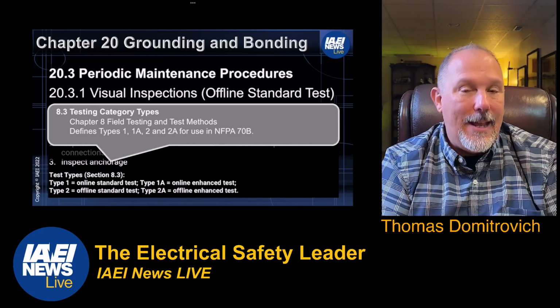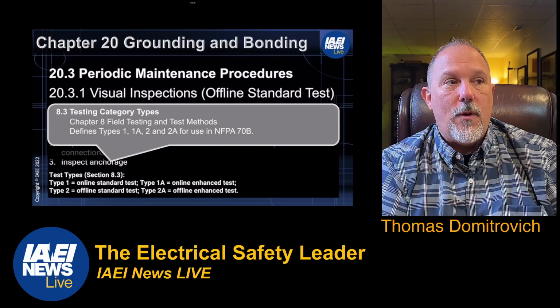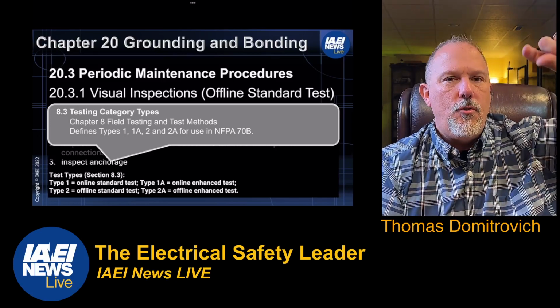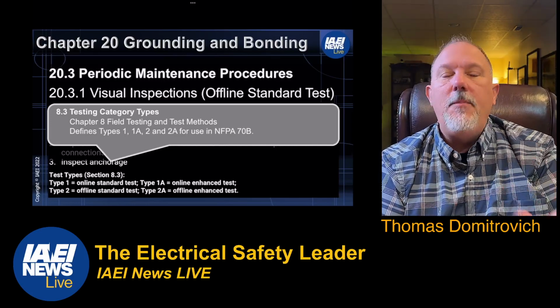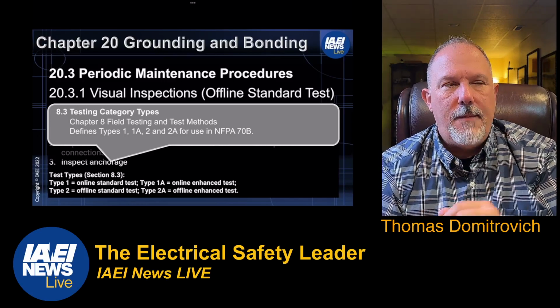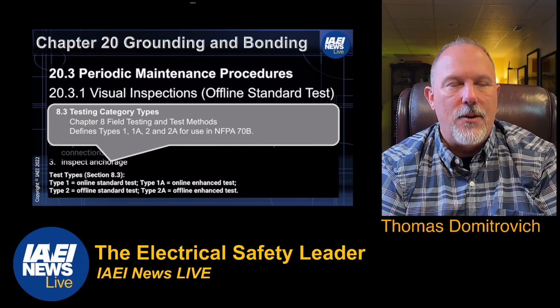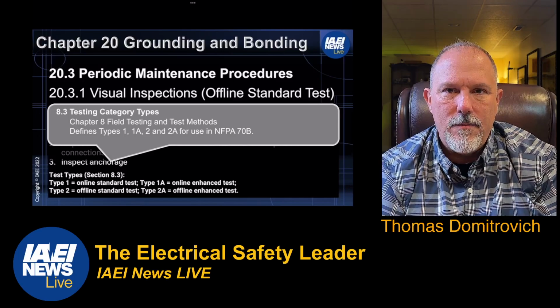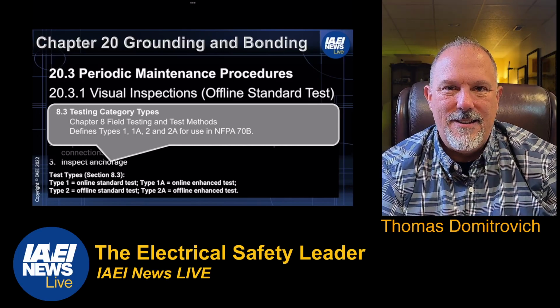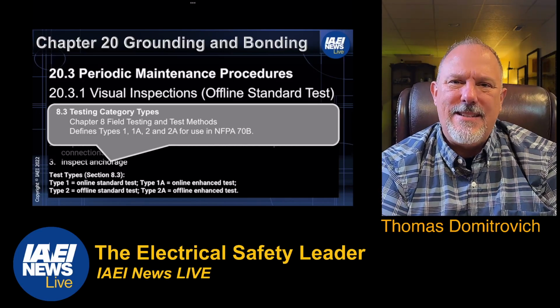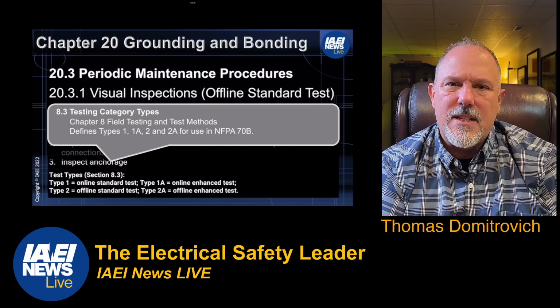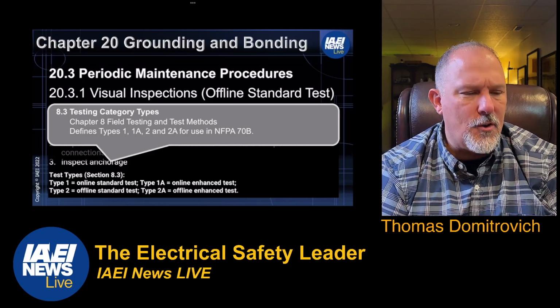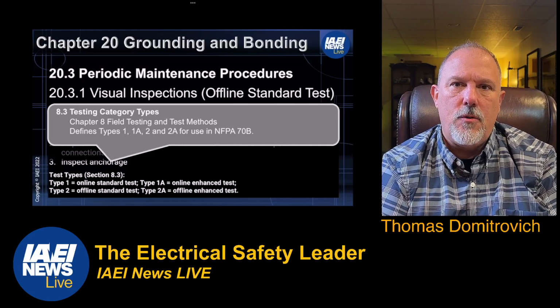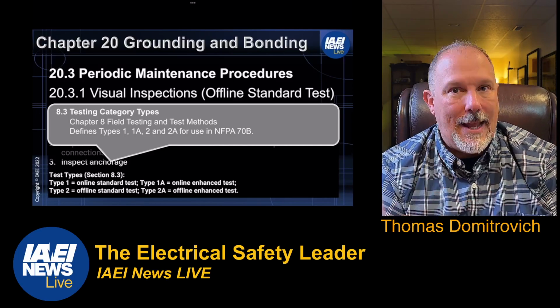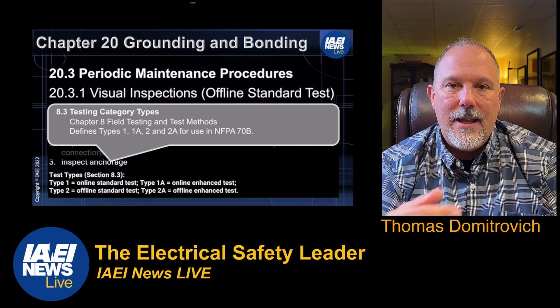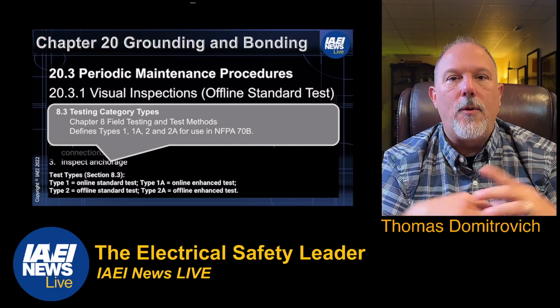And remember, your enhanced tests are for when, maybe you did thermography, and maybe a termination did not look quite right. It's on that borderline. It's not quite what you typically see in this equipment. It's not something you've ever seen before. You've done your homework. It's questionable. You may elect to do the enhanced test. Okay? An enhanced test is not, quote unquote, optional.